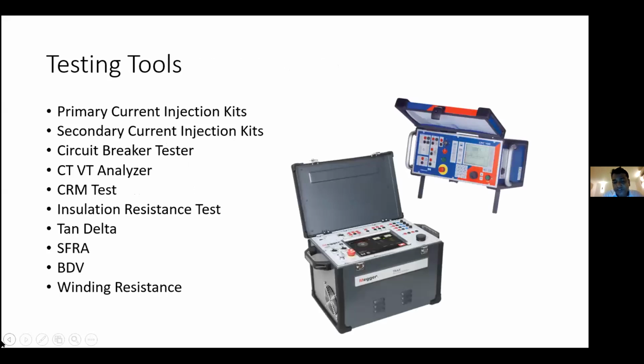To do this testing and commissioning, testing engineers use a lot of equipment. There are primary and secondary current injection kits, which are used to test relays and check whether the relay functions at the right current and right time. We use secondary current injection, and primary current injection to test the CTs as well.